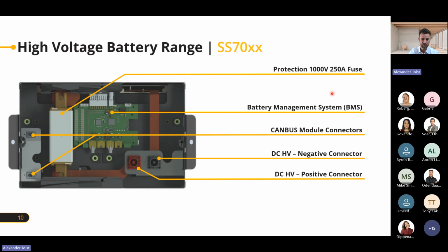If we look into it a little bit more in detail, each battery module has its own fuse protection here, which is a 1000-volt fuse and 250 amps. Each module will have its own BMS, so we can see within each of the batteries each cell detail, the voltage of each cell, and different temperature measuring points, which we have inside each of the batteries. At the bottom right, we have the DC connection points, and on the left side, we have our CAN bus connectors.